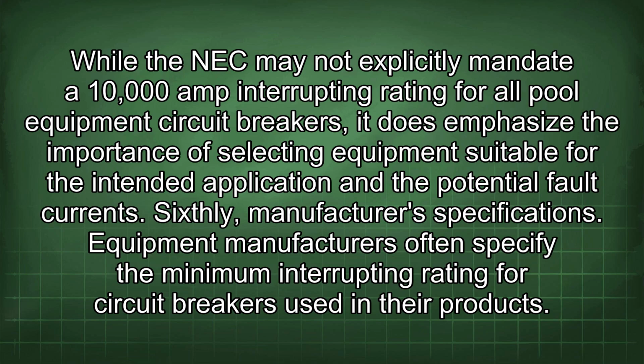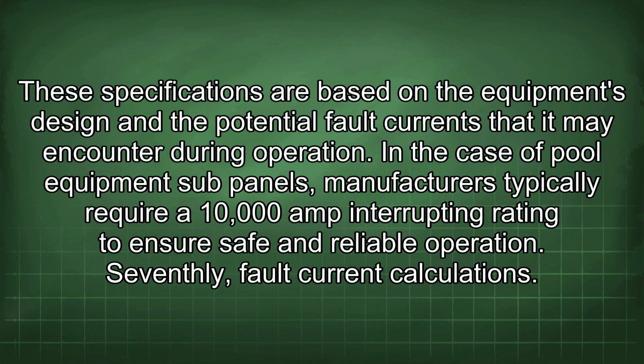Sixthly, manufacturer specifications. Equipment manufacturers often specify the minimum interrupting rating for circuit breakers used in their product. These specifications are based on the equipment's design and the potential fault currents that it may encounter during operation. In the case of pool equipment subpanels, manufacturers typically require a 10,000 amp interrupting rating to ensure safe and reliable operation.